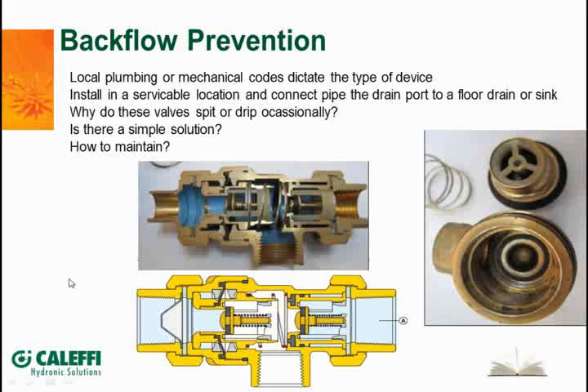So knowing that these can spit sometimes, the fact that they spit is telling you that they're doing their job. They're protecting what you're intending to be protected by spitting the water out of this vent. And so when people say, well, it spit water out, well, it might have spit water out because that's what it's supposed to be doing. But let me show you how they're built inside so you can understand where the spit's coming from, why it's coming, and what you can do to maintain, clean out, or repair it so you don't have to just throw them out all the time and replace them.